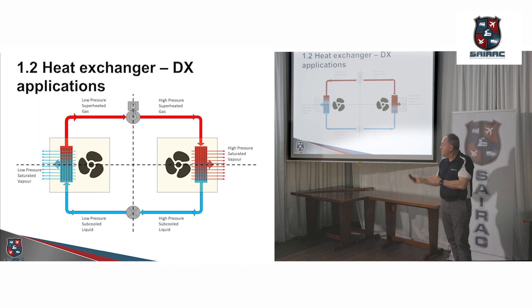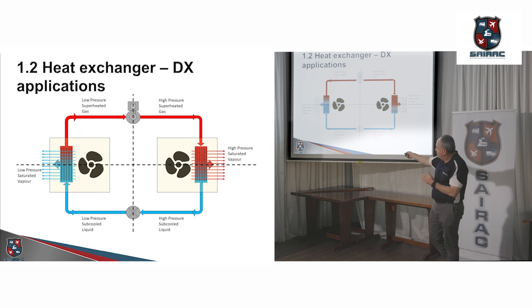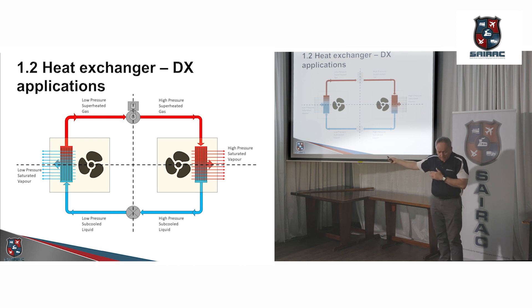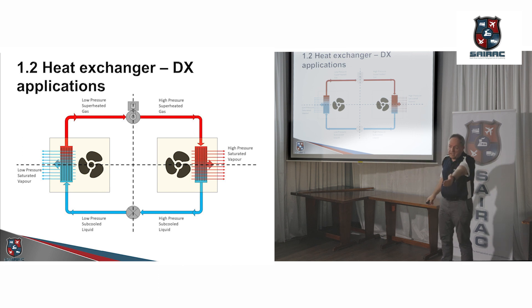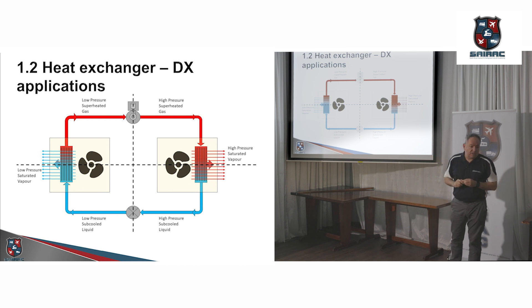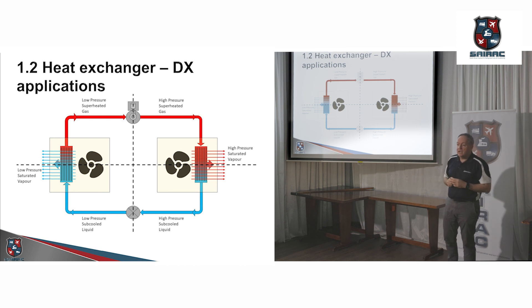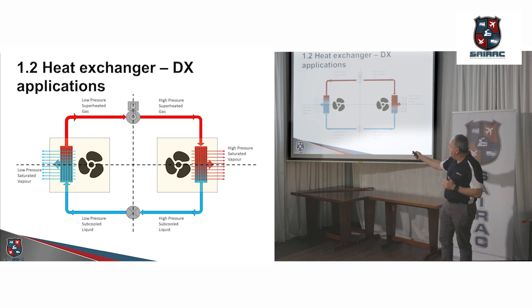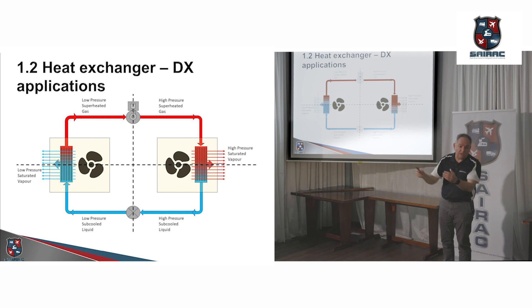A good illustration — try to memorize this: start with a vertical line. Your compressor is on the vertical line, one half on the low pressure side, one half on the high pressure side. Similarly at the bottom, your expansion valve is fed from the high pressure side and feeds into the low pressure side. The condenser is on the high pressure side, so a reading there gives your high pressure reading, and a reading at the evaporator gives your low pressure reading.